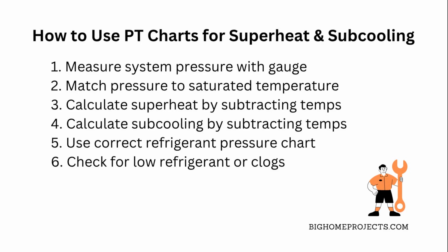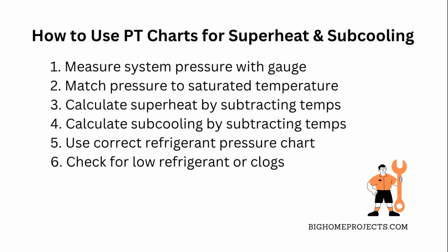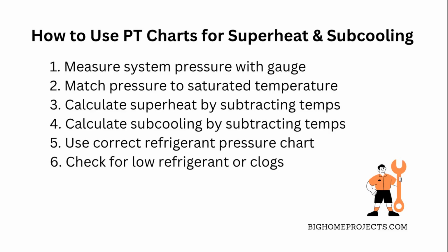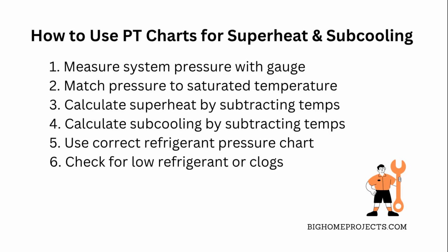Subcooling works the other way. You measure the liquid refrigerant temperature after the condenser and subtract the actual temperature from the saturated temperature. This shows how much cooler the liquid is below its boiling point, making sure your system's ready to cool efficiently.